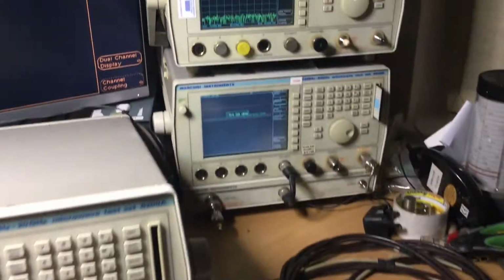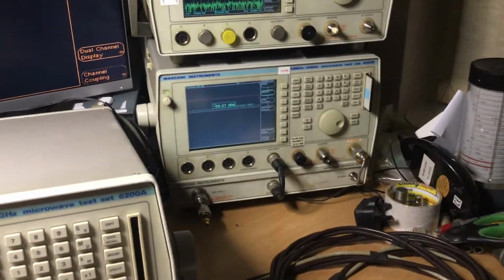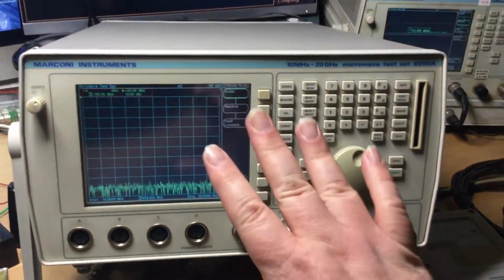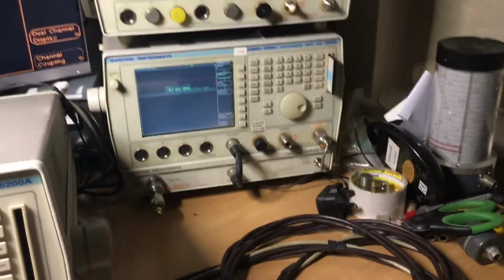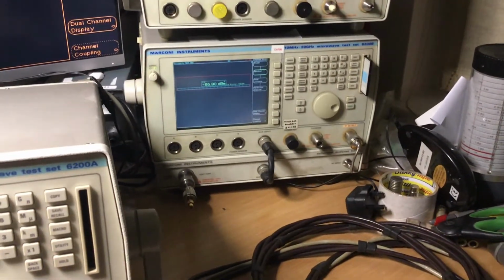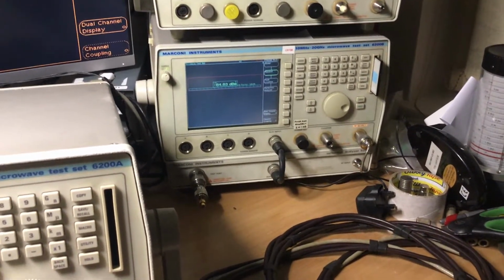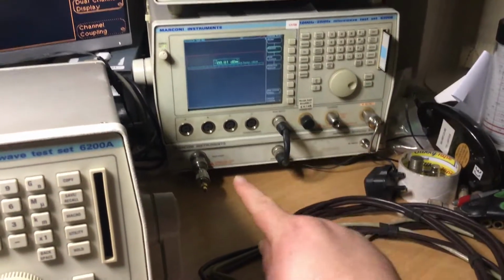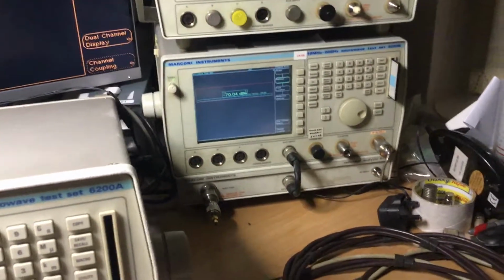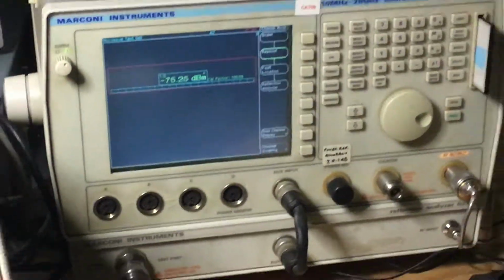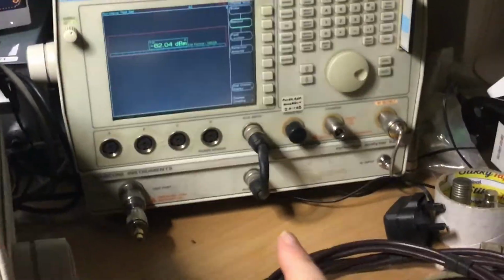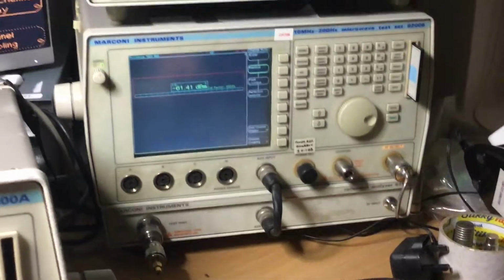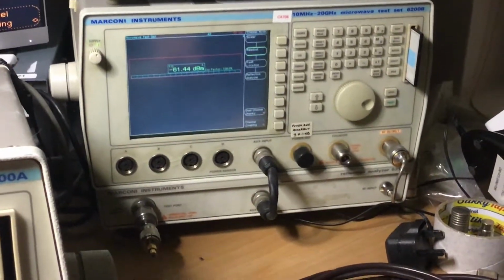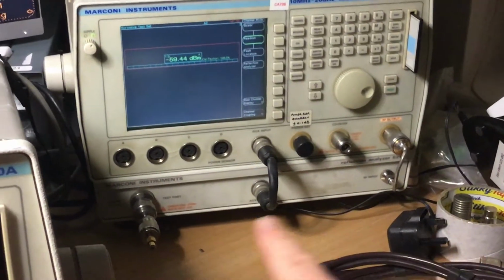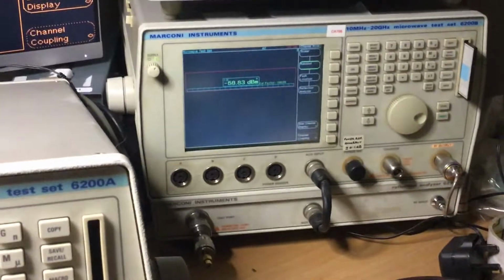But briefly, we've got the 6200A, which is this radio test set here that you see before you, and then we've also got the 6200B that's got a disk drive in it, and it's got the reflection analyzer at the bottom, a 4-port reflection analyzer, and that allows us to make S parameter measurements on a 4-port system. That is a 6210 that's added at the bottom there, just for reference, in case you're interested later on.